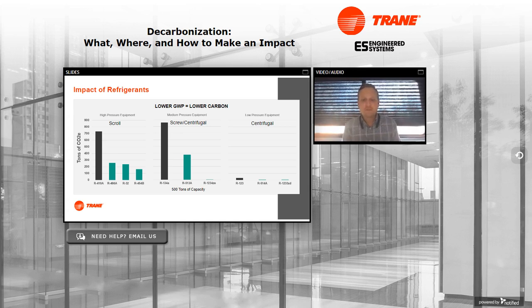This example is all for 500 tons of cooling capacity. Let's say you had a project where you needed a 500-ton chiller. You could lay out R134A at 500 tons, and that unit would contribute about 850 metric tons of carbon equivalency, meaning the refrigerant inside the chiller has 850 tons of carbon. Conversely, depending on where you're at in the world, you could use R1234ZE. In North America, there is 514A and 1233ZD available, and you can see the difference from 850 down to 10 metric tons.